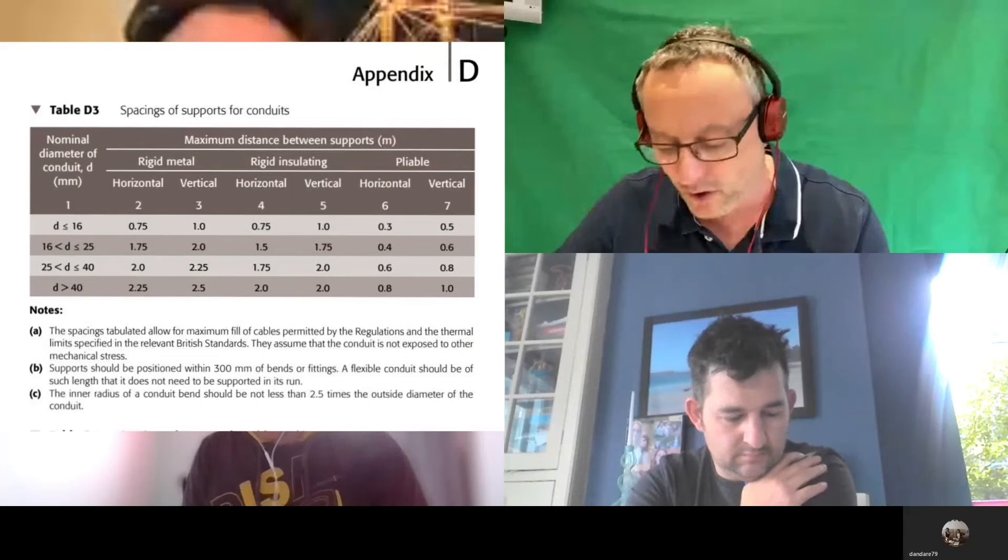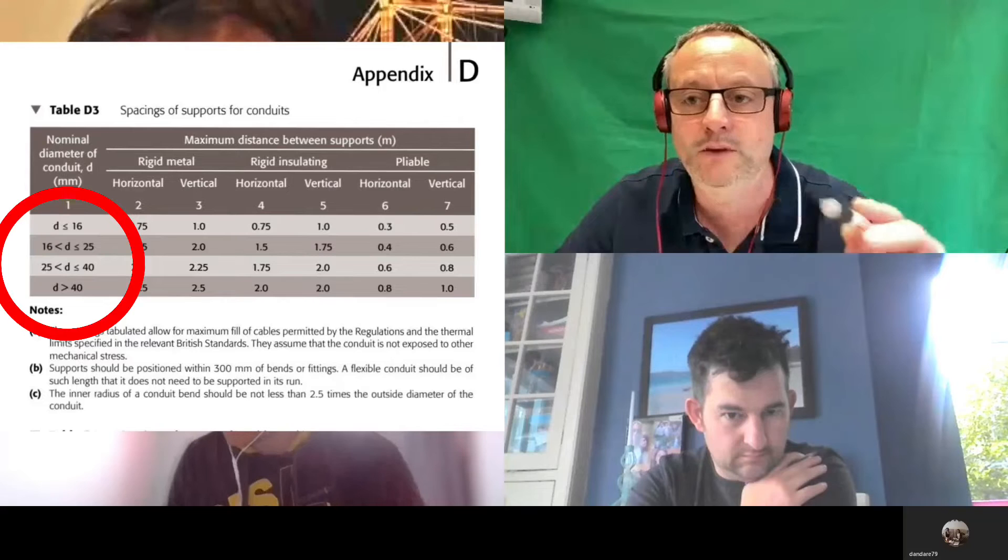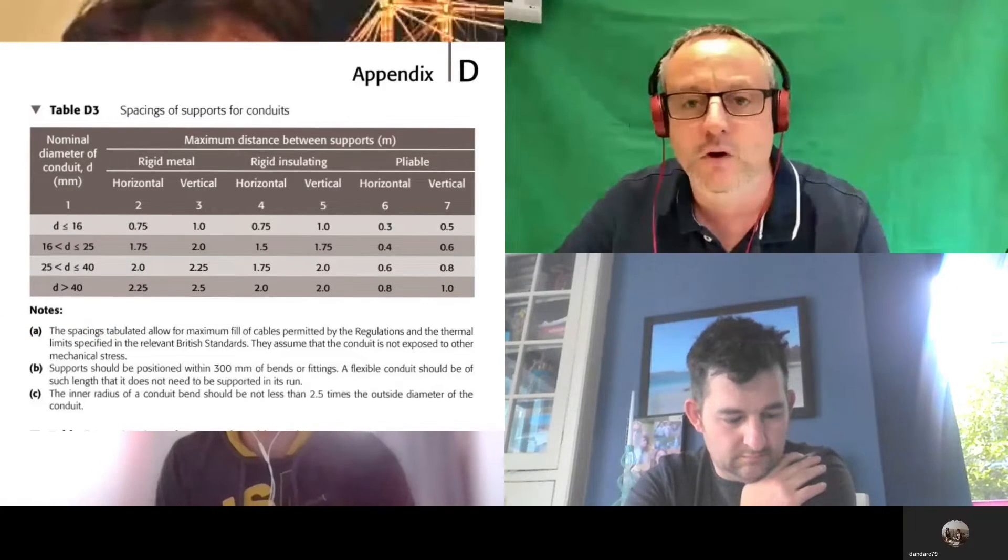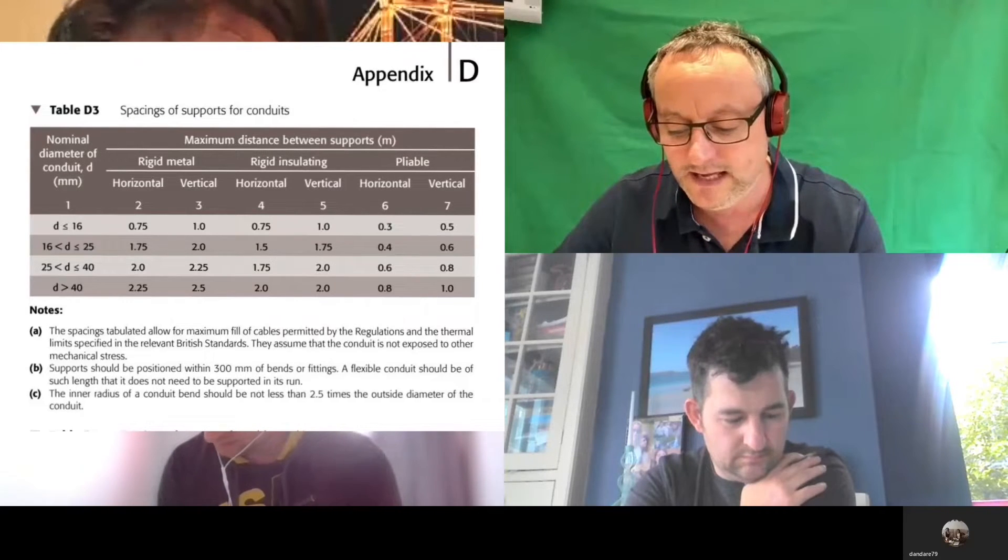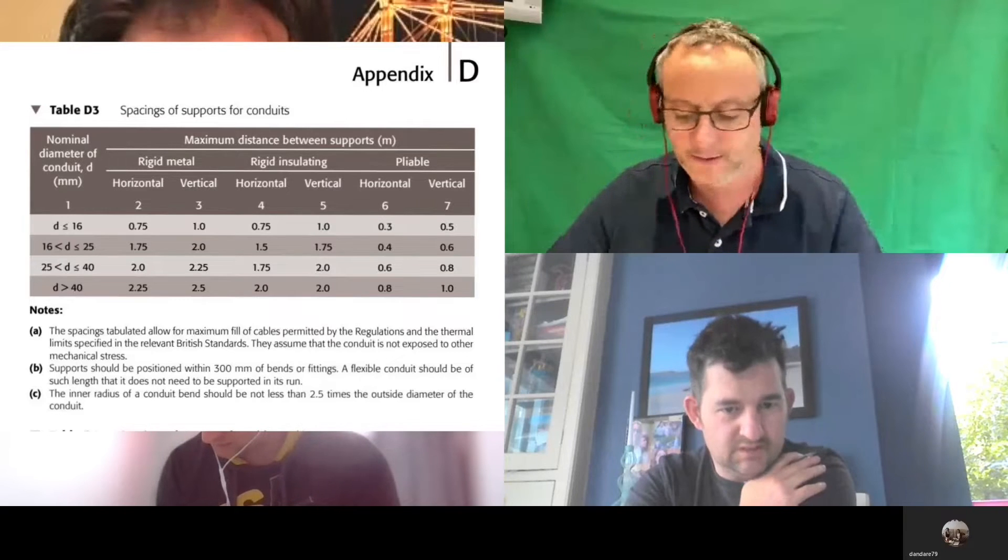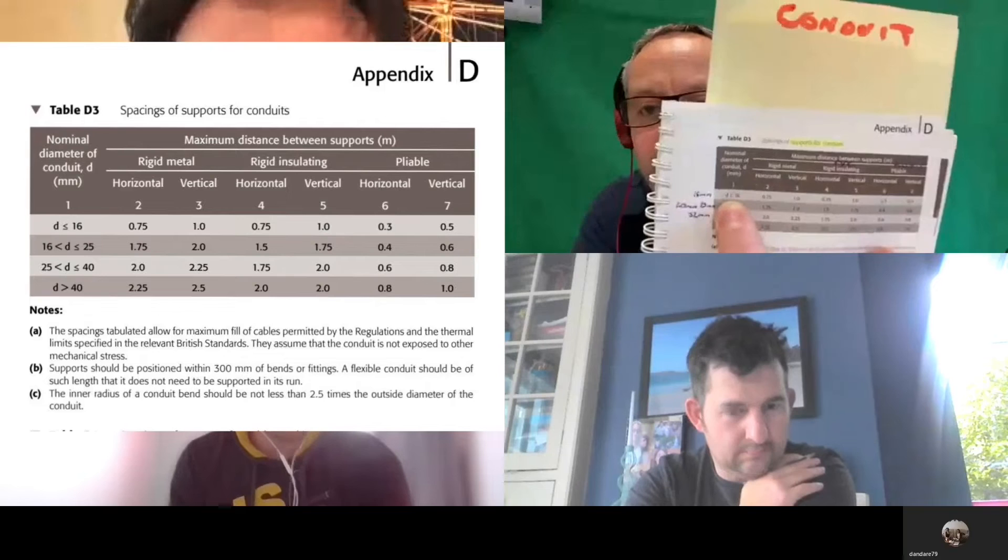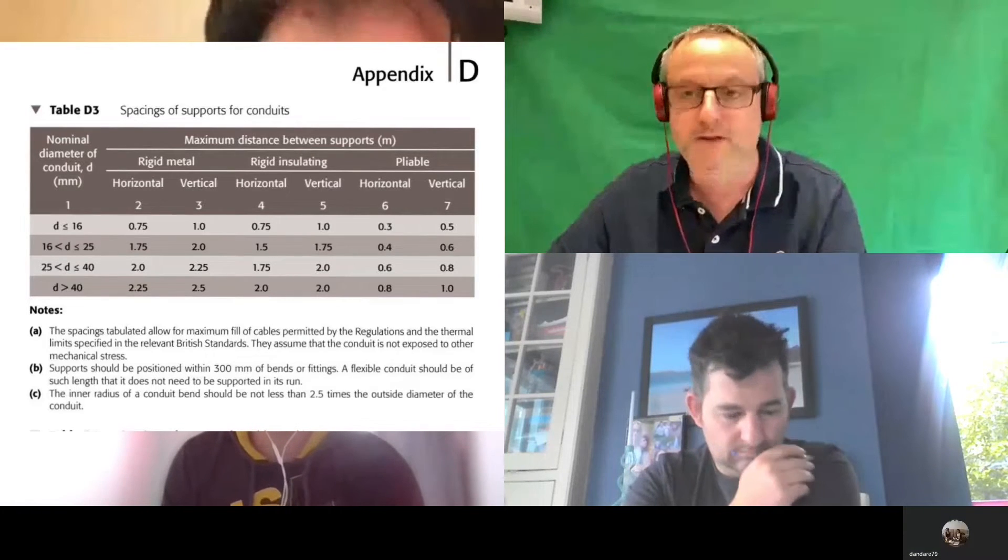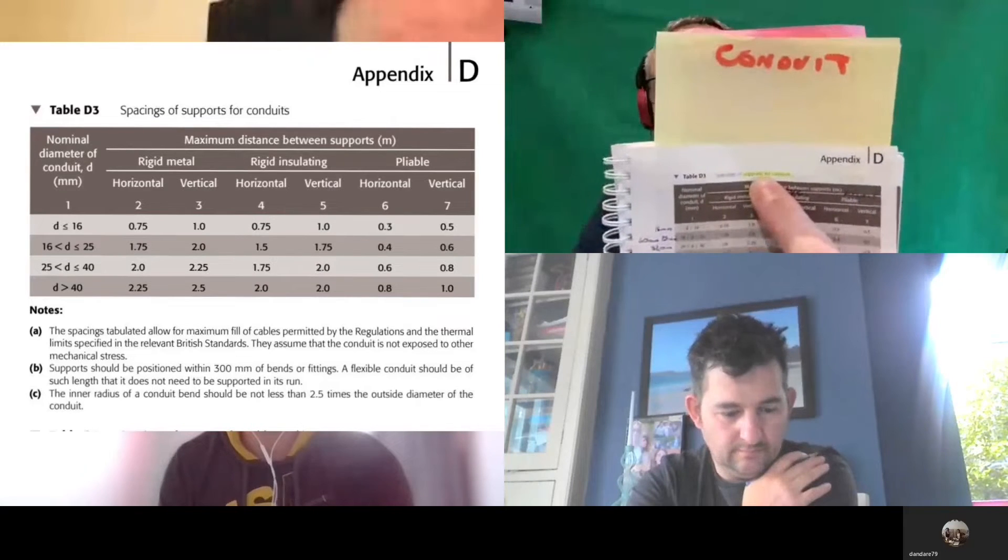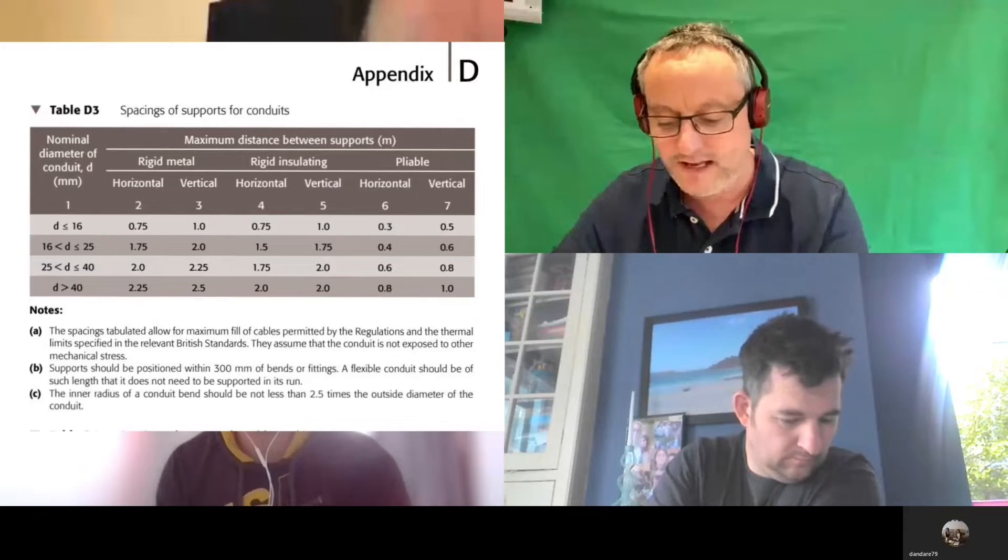Column number one is really important to us. Column number one, which has caused some confusion—somebody even said when we did the one for cable supports of twin and earth that they thought I got it wrong. People are missing that bottom line out. The first diameter is in column number one: up to and including which size? 16. So we can clearly see that's now up to and including 16. This is talking about the diameter of conduit.